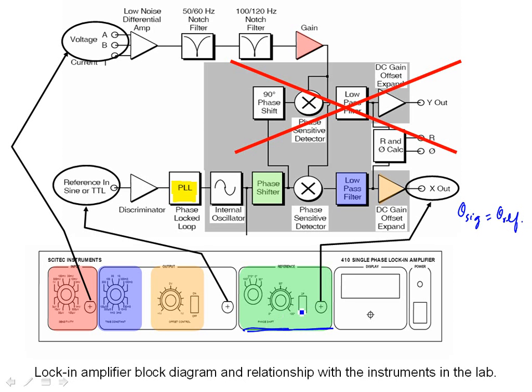Now, the reference frequency may be entirely generated by the lock-in, or you can also have external reference from the function generator, and that goes here. I'm sorry, the two things are switched here. This is actually the reference, and the output is here.